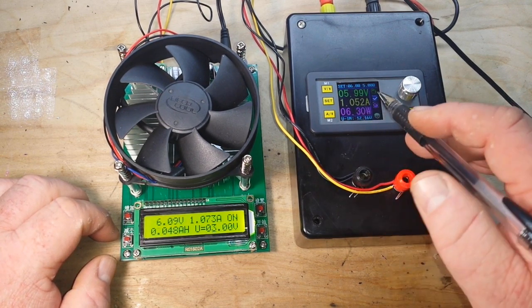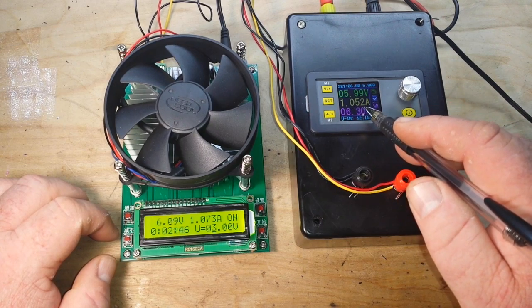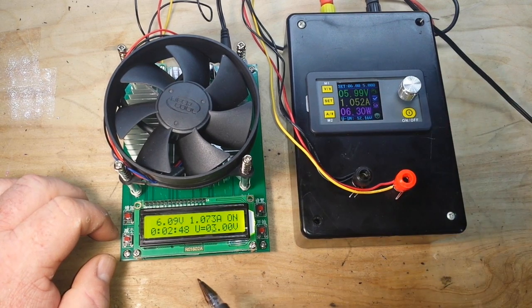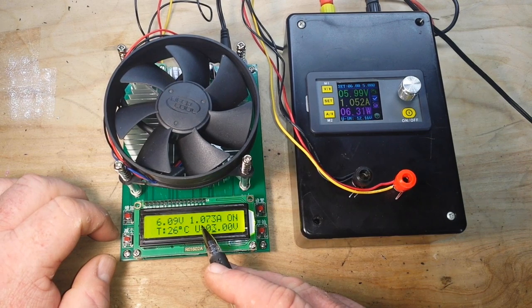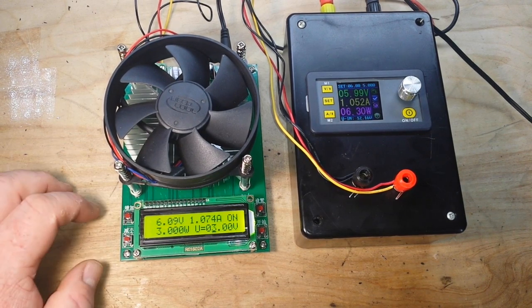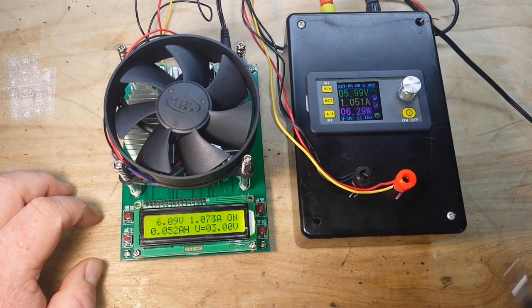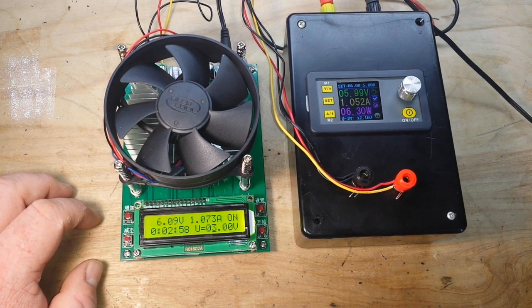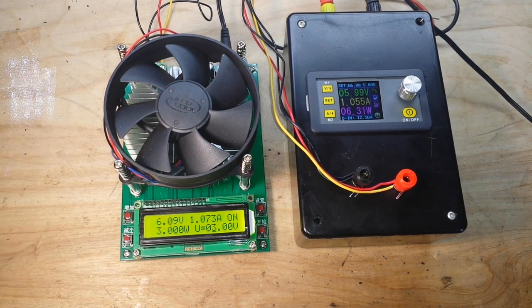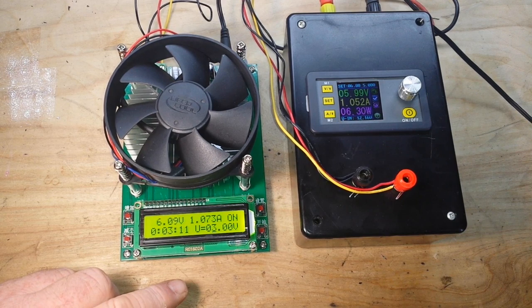So, okay, for our current setting, 1.052 amps going out, and we're seeing 1.073, so that's 20-some milliamps out. That is not super fantastic. I mean, I'm not going to diss on it for that, but I would like to see that be a little bit closer.